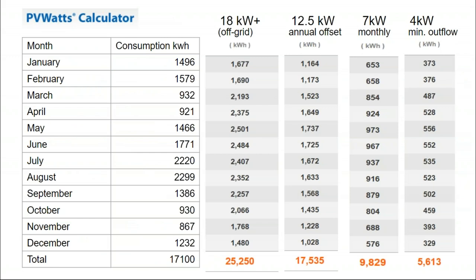Sizing the solar array can be spitballed based off the monthly consumption data, as can the size of the battery bank, because the battery bank is more concerned about having enough energy and not running out. So your 15-minute load versus your 1-hour load are less important when you're trying to store a day's worth, or 2 or 3 days worth, of power.